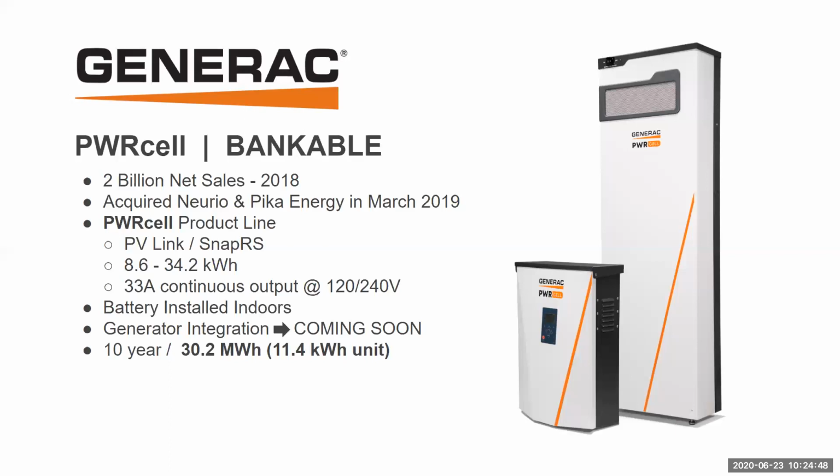And this is a really important thing to note, because if we have 15 kilowatts of PV, we can take, let's say, 7.6 kilowatts and invert that and go straight to the loads, but then any excess PV power can be used to charge the battery bank. So the reason you would want to oversize this, I don't even want to think about the AC-DC ratio, that 130% rule, if you're familiar with that, isn't really applicable in this DC coupled case, because we're prioritizing charging the battery first, and then we're able to feed the loads. So even though 15 kilowatts may seem like way too much for a 7.6 kilowatt inverter, we're not going straight to the loads. We have charging the battery to prioritize too, so it really is advantageous.